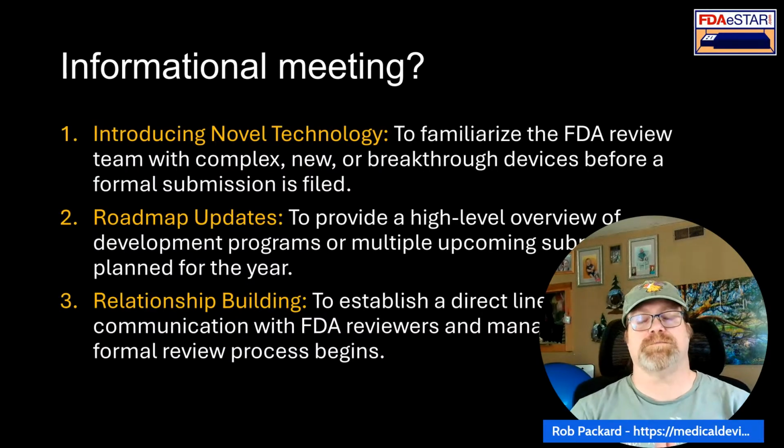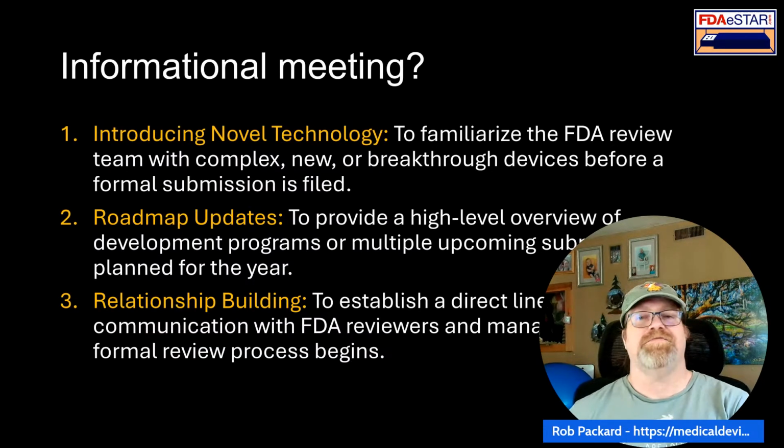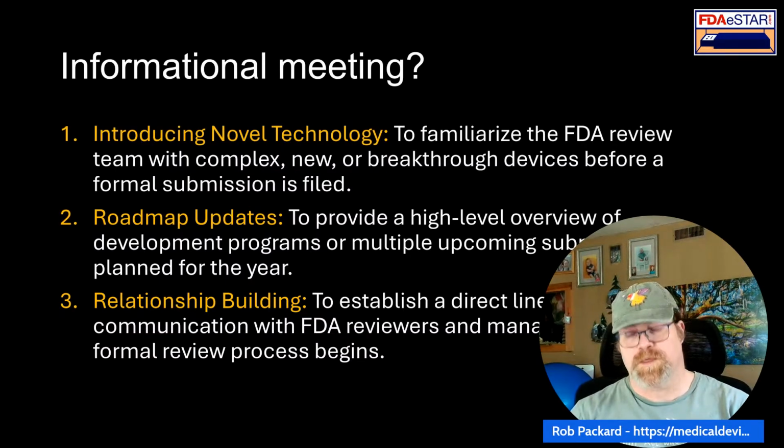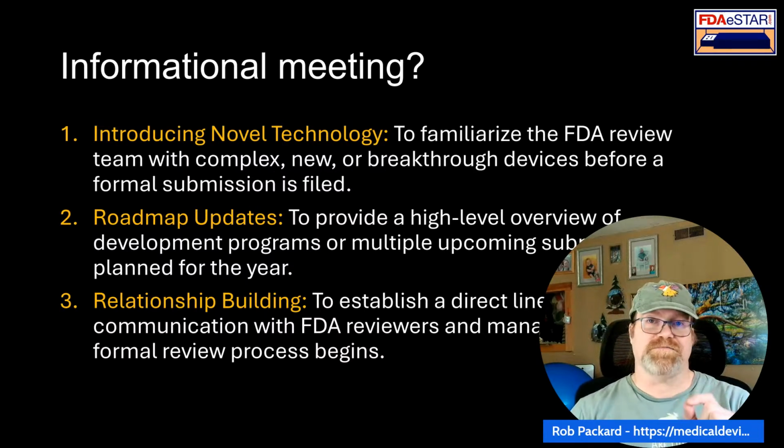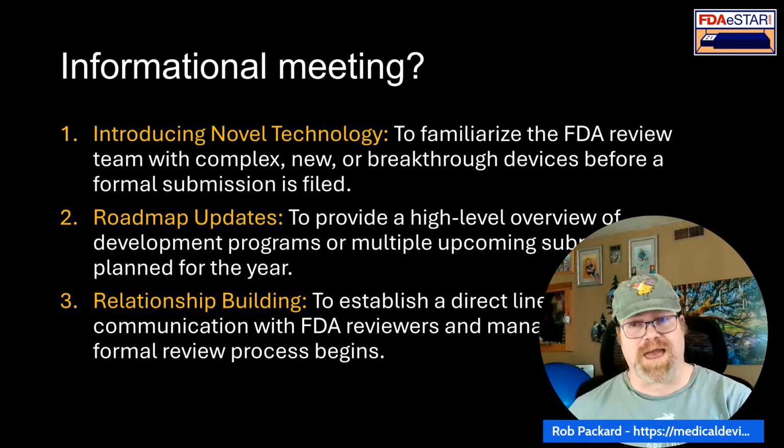And then there's going to be a new species of infectious disease that you're going to detect that requires a de novo, but you want to multiplex it with all the 510(k) ones. That creates a problem because you can't combine 510(k) and de novo in the same submission. So you have to get your de novo first, and then after your de novo is granted, then you can combine that with your other multiplex tests in a 510(k) and release the new multiplex tests.